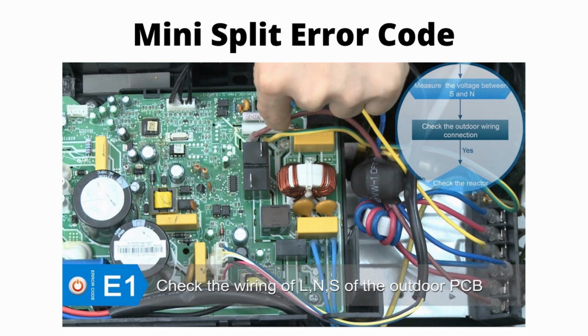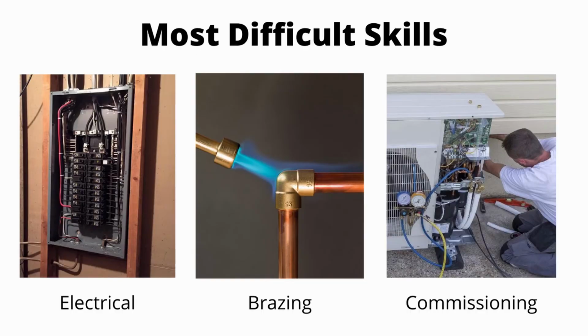If it is not working, you will need to investigate the error code and check that you have electricity to the units. Now that you have examined the steps necessary to install a mini split, we can categorize the skills needed. The three most difficult skills are number 1, electrical, number 2, brazing the line sets, and number 3, commissioning the unit. Electrical can be difficult and dangerous if you don't know what you're doing. We recommend having a professional do this step.